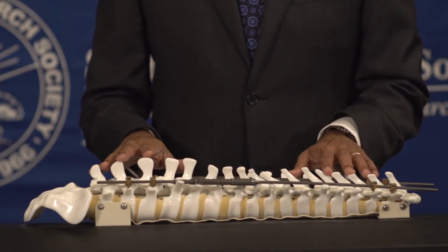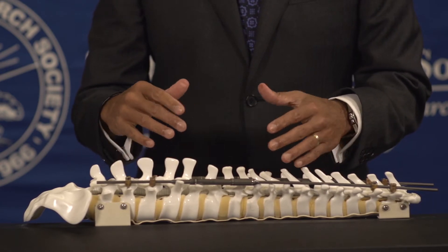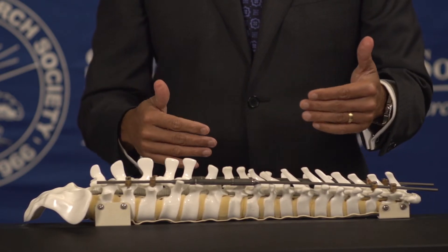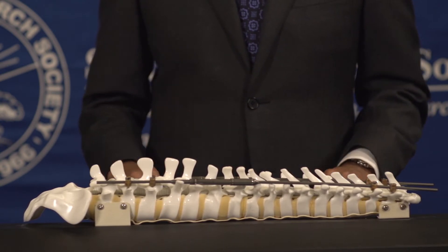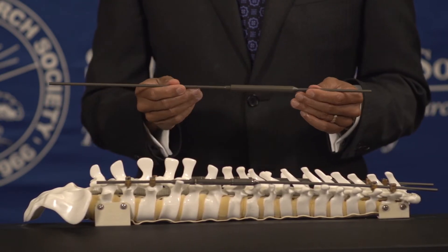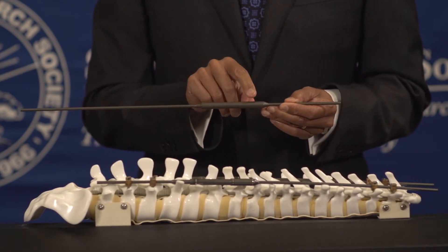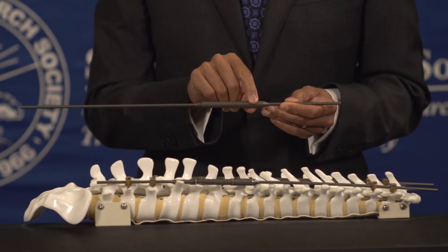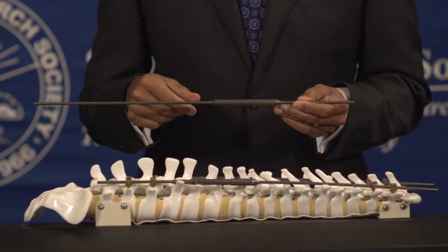This is a model of the spine that has two rods installed in different configurations so that a surgeon may be able to treat different parts of different curves or customize treatment during the lengthening process. This is a rod outside the model — the magnet or actuator lives on this side of the rod, and the rod can elongate through this portion, which we're going to illustrate on the model.